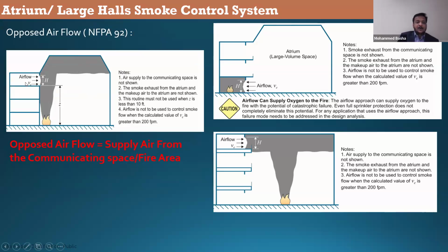It is intended to avoid smoke penetration from this area, which is the large volume area, to the communicating space. How it works: you will have a fresh air fan here, and you will be pushing the air with a certain velocity to keep the area smoke free. It is basically a kind of smoke containment methodology, but it does not create a pressure. That's why it does not come under smoke containment systems. It is still a smoke control system, because here there is no need to maintain different pressures, which is the pressure differential delta P we measure in the staircases. Here we are just flowing the air with a certain velocity to keep the smoke from coming out to the communicating space. This is called the opposed airflow method.